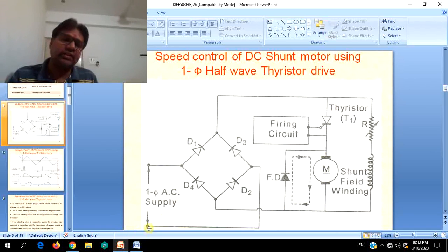During the negative half cycle, when the lower terminal becomes positive, or becomes the phase, the voltage will now be supplied via D3, SCR and armature, and back to the supply source via D4. In both half cycles, the direction of applied voltage as well as current through the armature as well as field will be the same. So it is a unidirectional current, UDC as we know it.